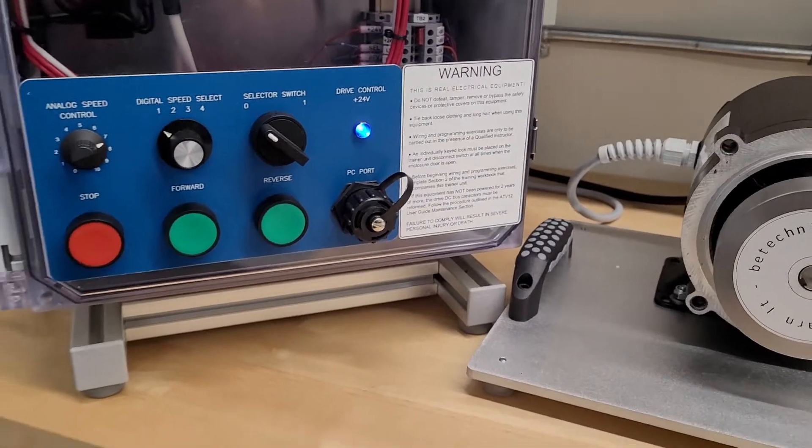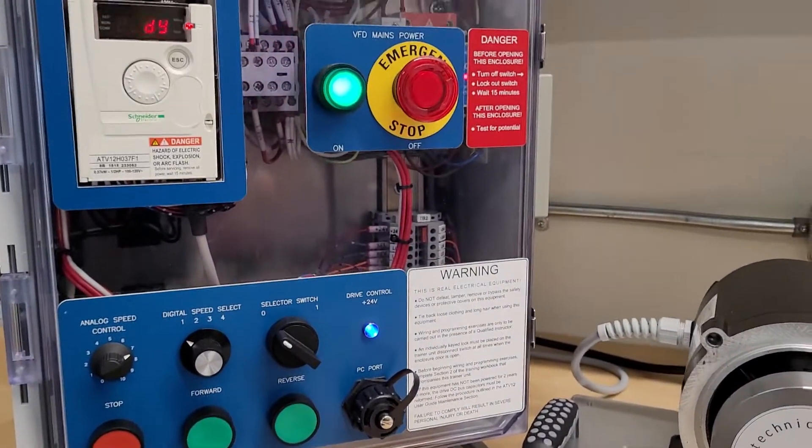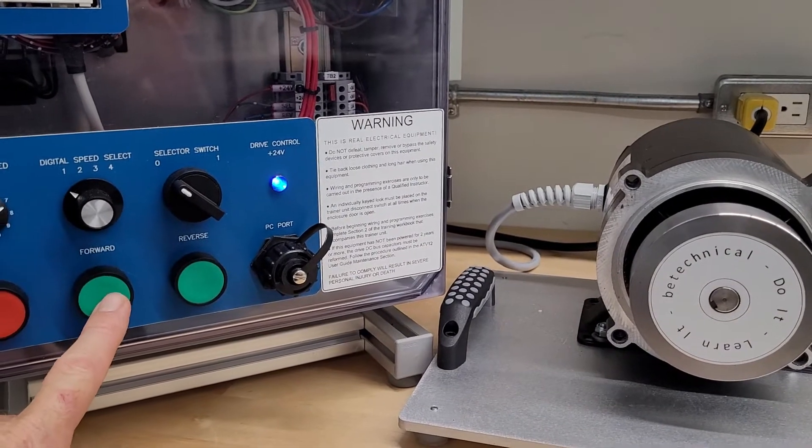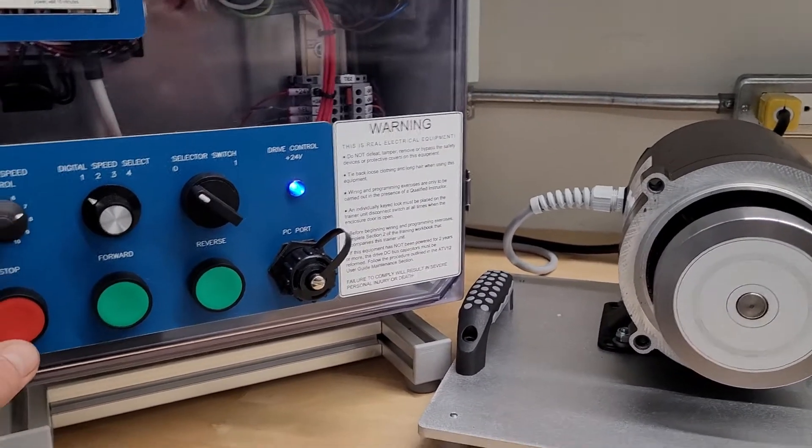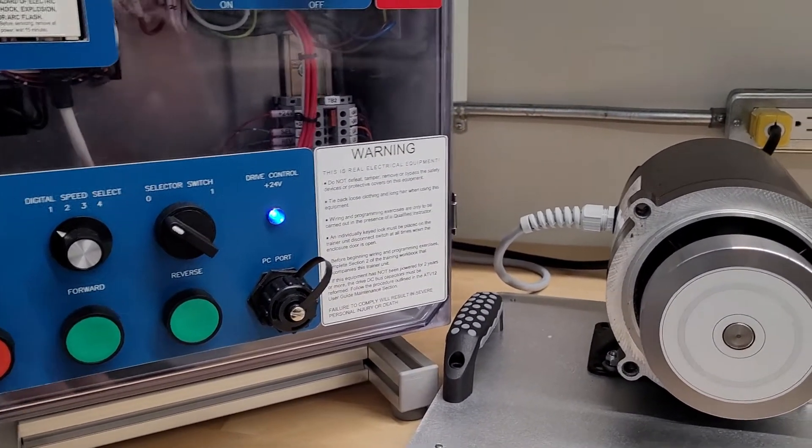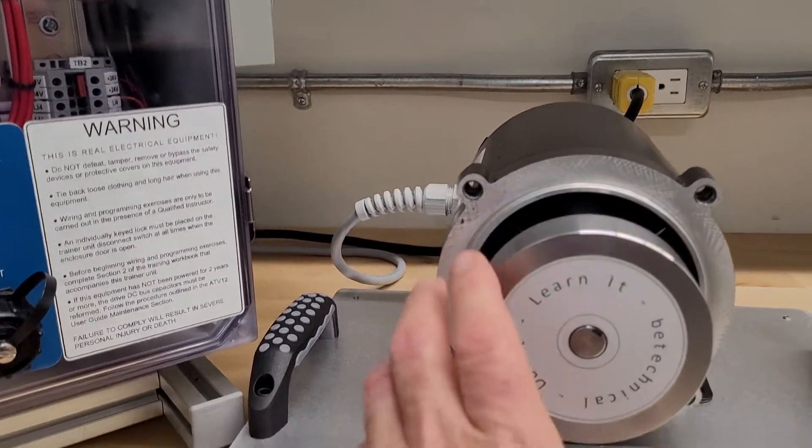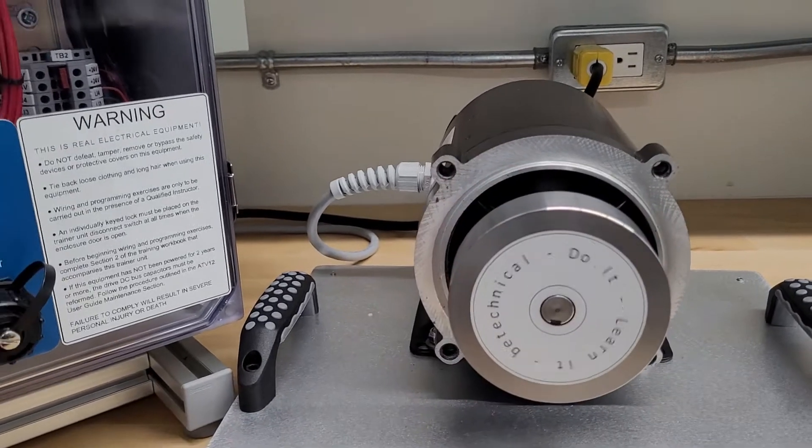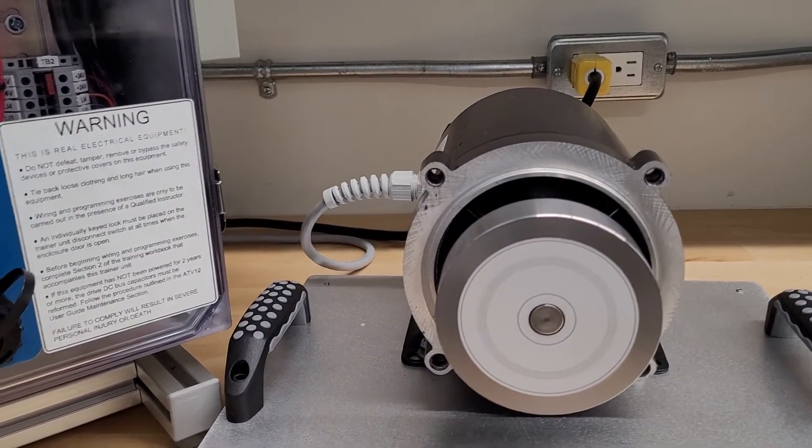So on this little ATV 12 drive I have one-third horsepower set up on three wire control. If I hit start and stop, got a two-second deceleration ramp, you'll notice I can just spin the rotor right. So it can freewheel. That works in either direction if I start and stop it.